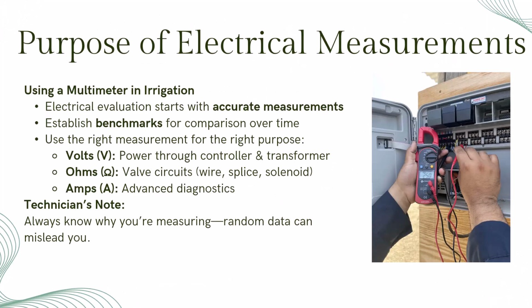Before you start taking any measurements, know what you're testing and why. Every accurate electrical diagnosis begins by establishing a baseline, a benchmark to compare against future readings. In irrigation troubleshooting, we measure volts to check if power is reaching where it should, controllers, transformers, and sensors. We measure ohms to check the resistance in valve circuits, including solenoids and splices. We measure amps only in advanced cases like diagnosing high power issues or motor loads. And always keep in mind, collecting random readings without purpose doesn't help. It confuses the picture and wastes time.